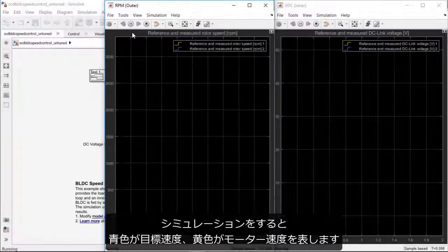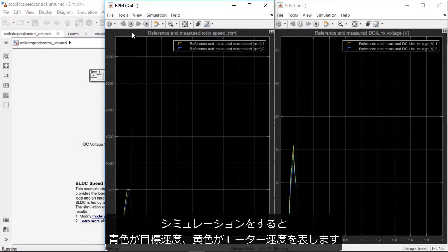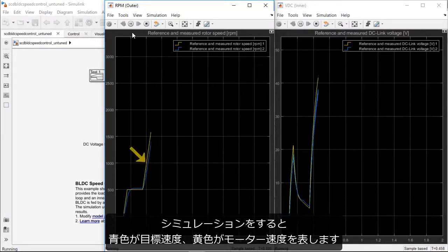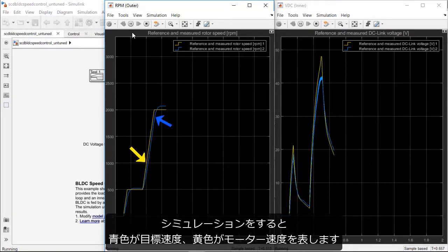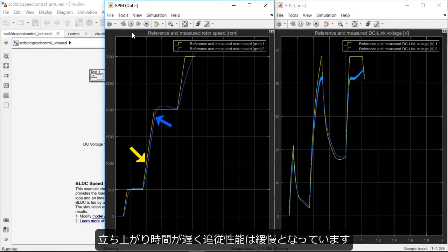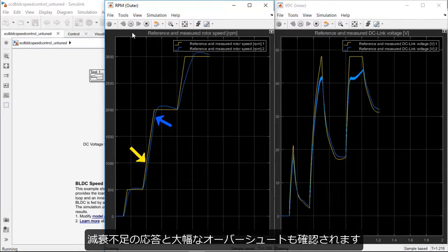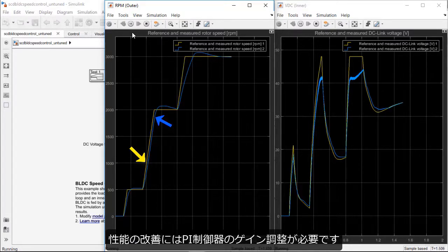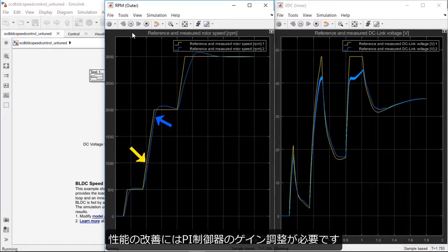When we run the simulation, we can see that the speed demanded from the motor in yellow and the actual motor speed in blue. The reference tracking controller performance is sluggish with a slow rise time and underdamped response and a significant overshoot. We will need to tune the PI controller gains to get a better controller performance with good reference tracking.